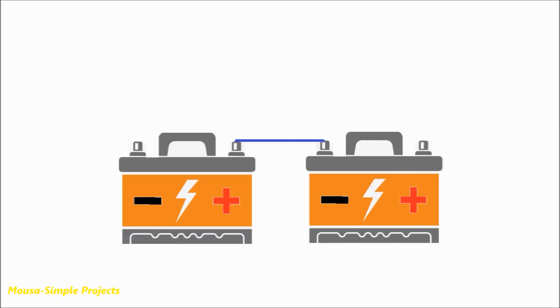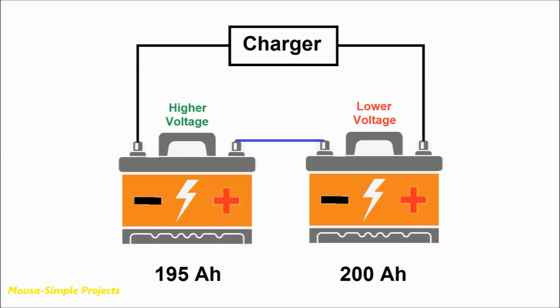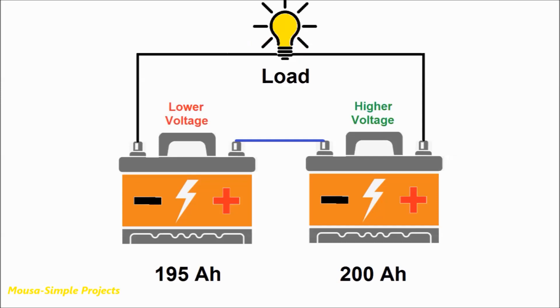The reason for that is because the real capacity of battery number one is slightly less than battery number two. Let's say the first battery is 195 amp-hours and the other is 200 amp-hours. So that means when you charge them together, the first battery gets fully charged before the other. But when you start to discharge them, this time the voltage of the first battery drops faster than the other because it has less capacity and drains faster.